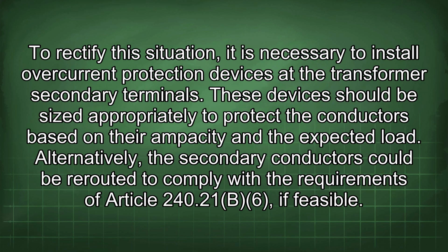To rectify the situation, it is necessary to install overcurrent protection devices at the transformer secondary terminals. These devices should be sized appropriately to protect the conductors based on their ampacity and the expected load. Alternatively, the secondary conductors could be rerouted to comply with the requirements of Article 240.21(B)(6) if feasible.